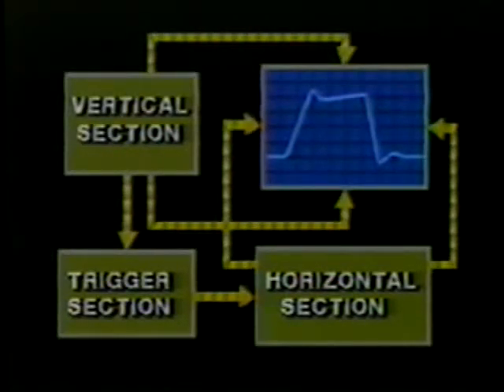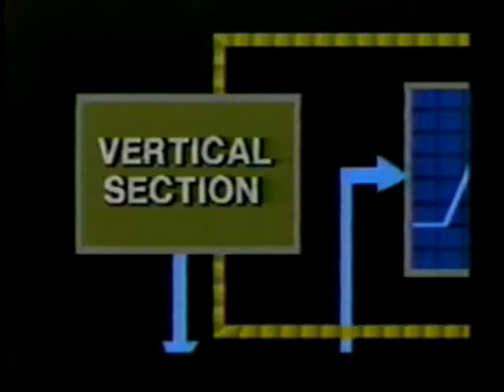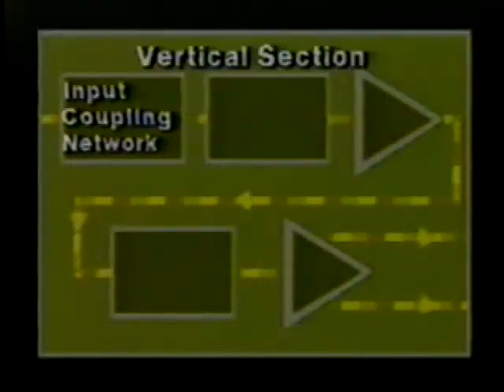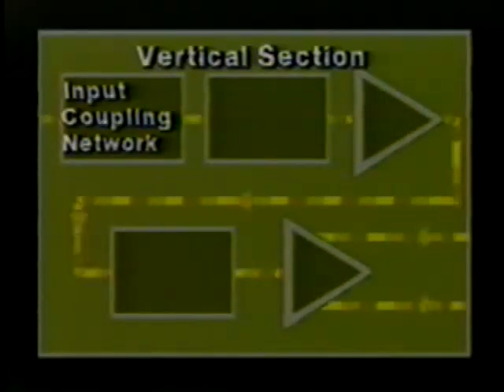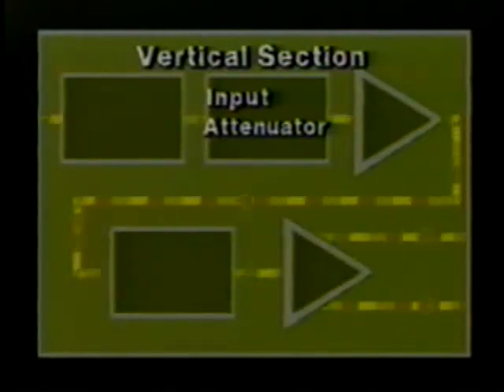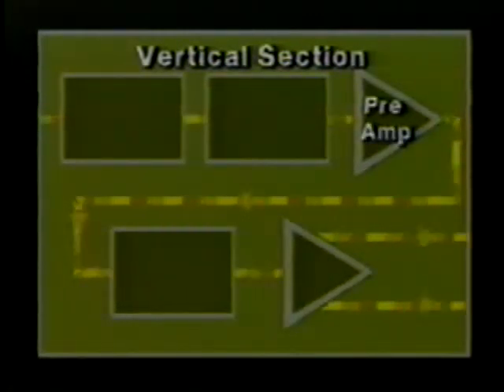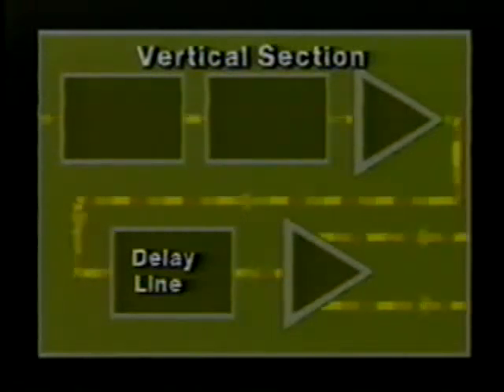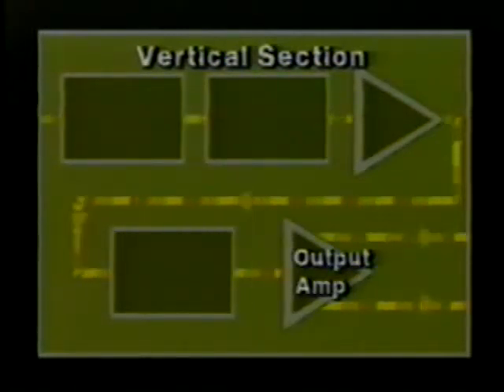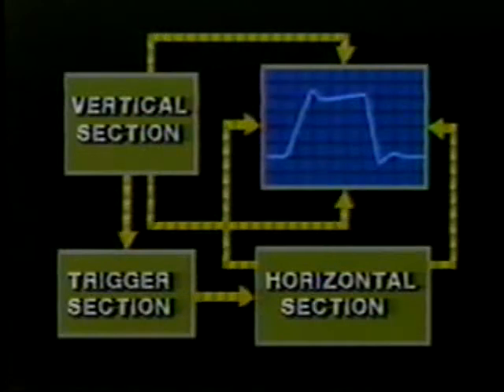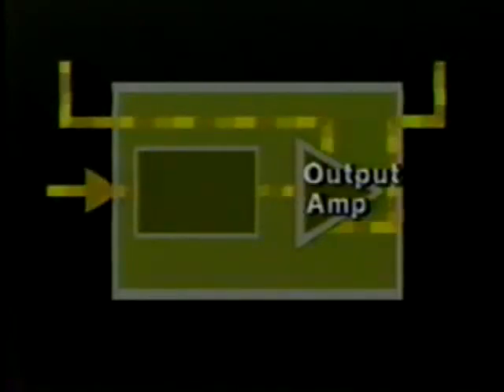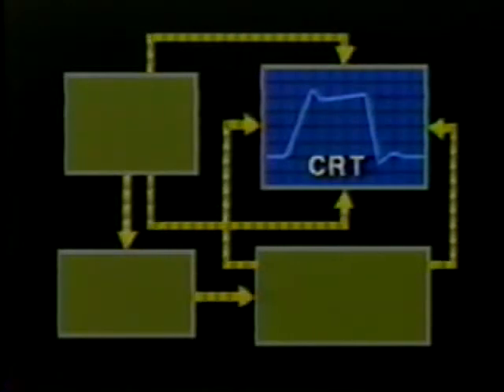This diagram shows the functional blocks commonly found in oscilloscopes like the 2235. The vertical section is composed of the vertical input coupling network, vertical input attenuator, vertical input amplifier, the delay line, and vertical output amplifier. The horizontal section includes the trigger circuit, horizontal sweep generator, and horizontal output amplifier. And finally there's the cathode ray tube, the CRT.